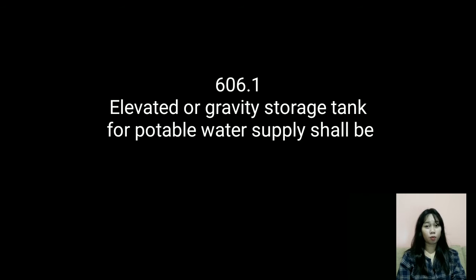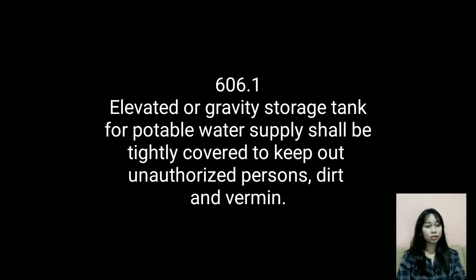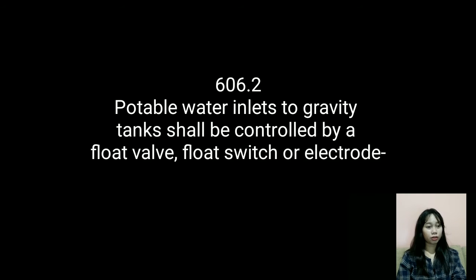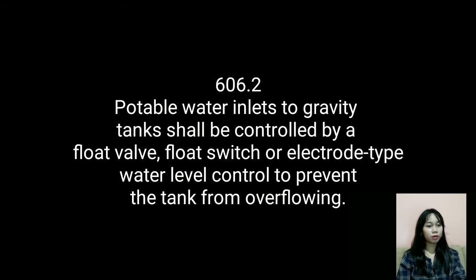In Section 606.1, elevated or gravity storage tanks for potable water supply shall be tightly covered to keep out unauthorized persons, dirt, and vermin. The covers of gravity tanks shall be vented with a return vent pipe having an area not less than the area of the down-feed riser pipe, and the vent shall be screened with a fine corrosion-resistant screen with openings not less than 14 nor more than 18 mesh per 25 mm. In Section 606.2, potable water inlets to the gravity tank shall be controlled by a float valve, float switch, or electrode-type water level control to prevent the tank from overflowing.